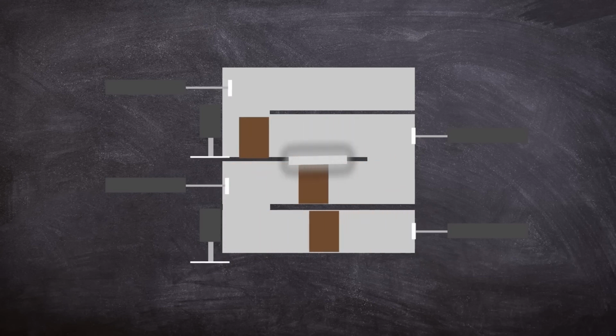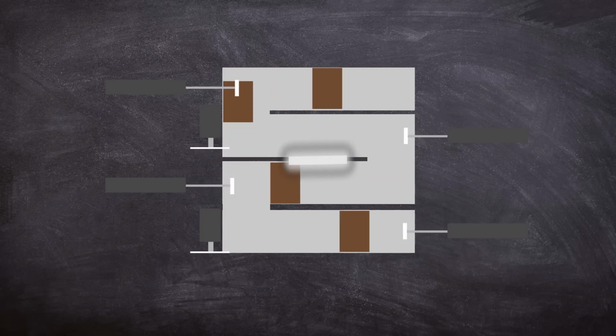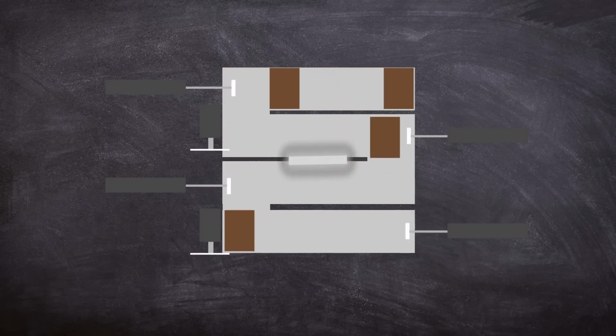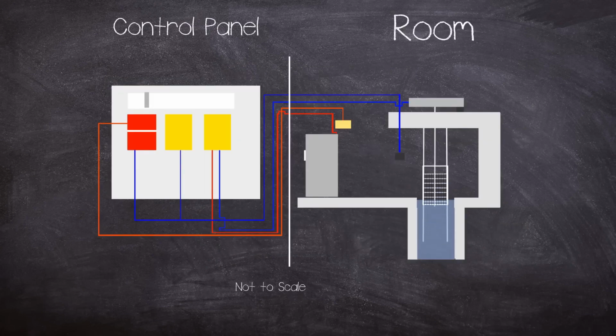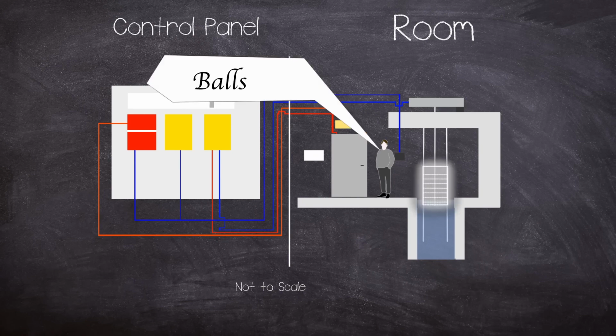During an irradiation cycle, access to the room has to be restricted because of the high risk of exposure to the cobalt-60. The irradiation room had a number of controls to prevent A. access to the room when the source is out of the pool, and B. the source being raised when someone is in the room. This was designed into the system by AEC Limited, and a vital part of this was the machine key.